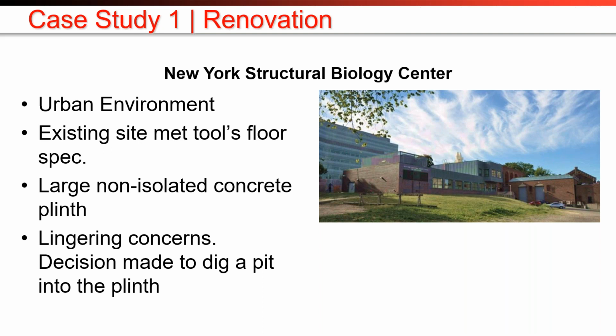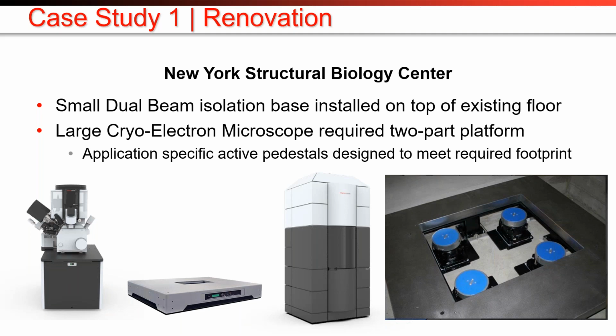And there were lingering concerns that city activity changing over time would impact future tool performance. And there really wasn't any sort of upgrade path or any plan they could come up with to lower the vibration levels if the plinth turned out to be not an adequately quiet environment. So the decision was made, during the renovation, to dig a pit into the existing plinth. And I'll show that pit in the next slide.